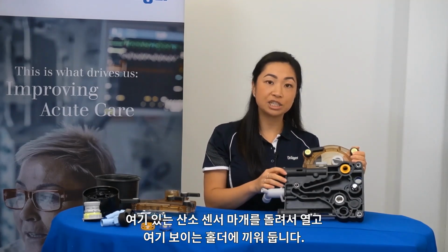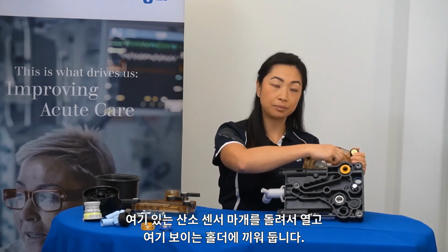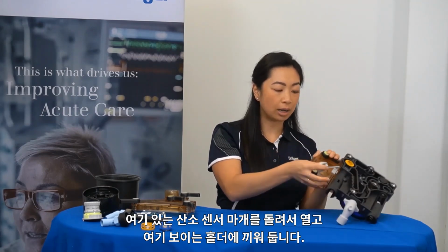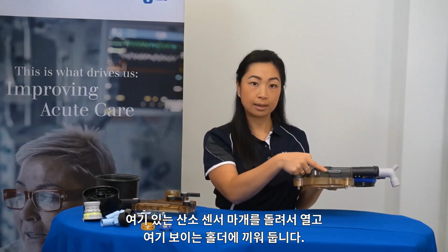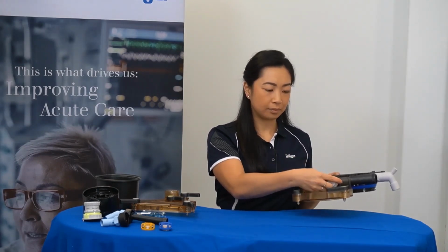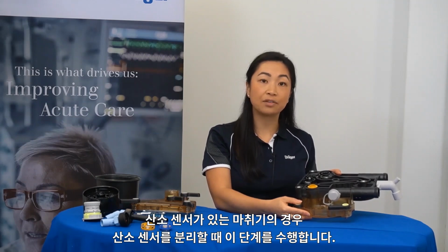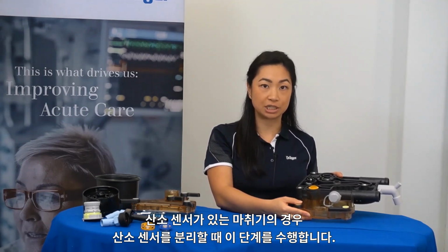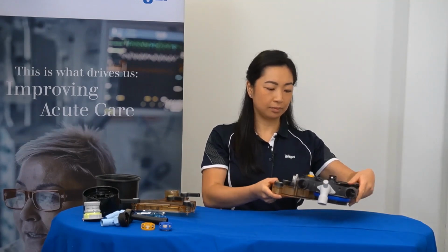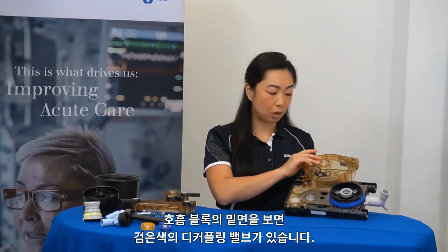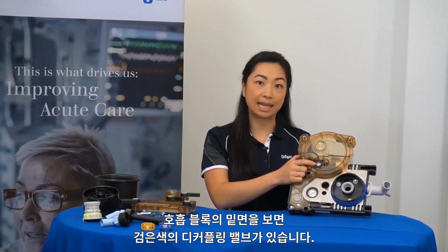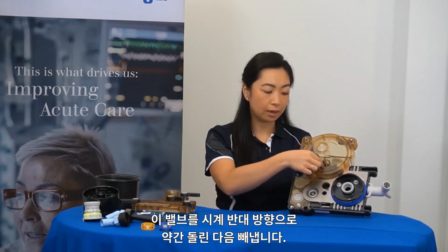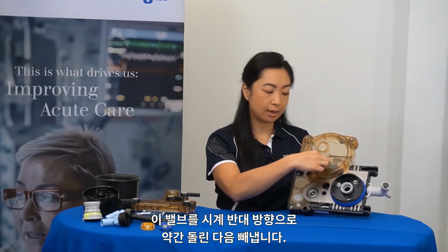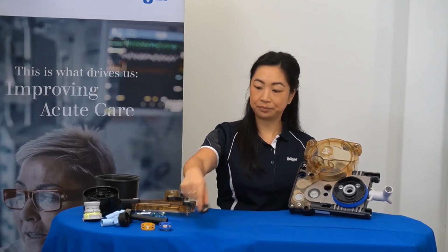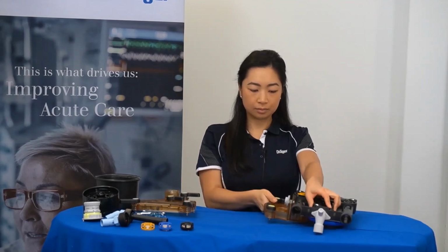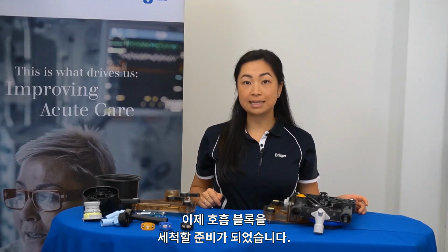From here, the oxygen sensor cap can be unscrewed and placed into the holder that is seen here. For the devices that have an oxygen sensor, this is when you'd remove the oxygen sensor. Now on the underside of the breathing block, you'll find the decoupling valve that is black in colour. To remove this valve, a slight anti-clockwise turn and then pulling it out. Your breathing block is now ready for cleaning.